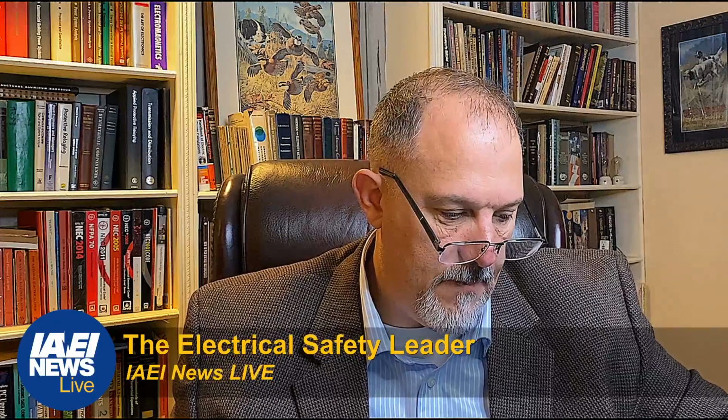And now in hearing protection, the change they made in hearing protection was pretty simple. Remember, there was a requirement that said you had to have hearing protection when you're working inside the arc flash boundary. So what they said now is, look, you don't have to be working in the arc flash boundary. You just have to be merely in the arc flash boundary, and you need that hearing protection. So they removed the reference that you have to be working, because, technically, if you're in that arc flash boundary, you better be working.